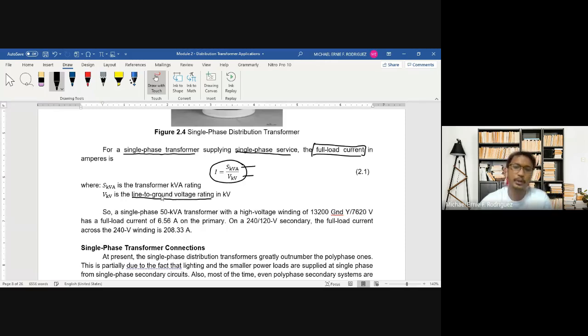For example, if you have a 50 kVA transformer, and the high voltage winding is 13,200 GRDY or GNDY, which has 7620 volts, we take the line to ground rating, which is 7620 volts. So we have our 50 kVA and 7620 volts.